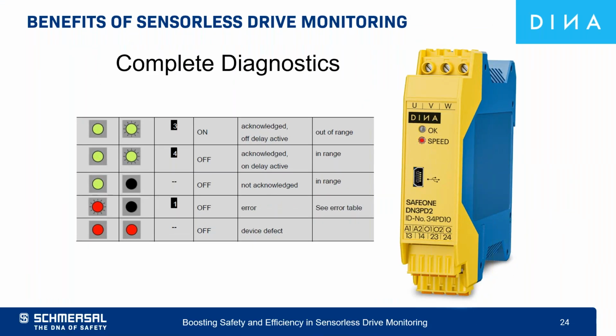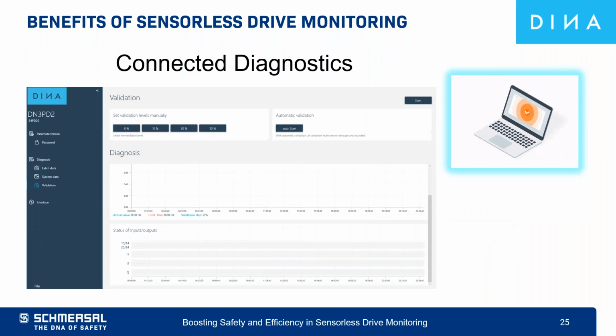For diagnostics, DINA offers two different methods to obtain quick information. Method one, the running status and the fault status are both displayed proudly on the front panel of the speed monitoring units for quick access. Method two, the use of the free proprietary software Go Beyond from DINA, which allows you to see not only real-time data, but real-time faults for diagnostics. This software is very intuitive for anyone who understands motor terminologies.